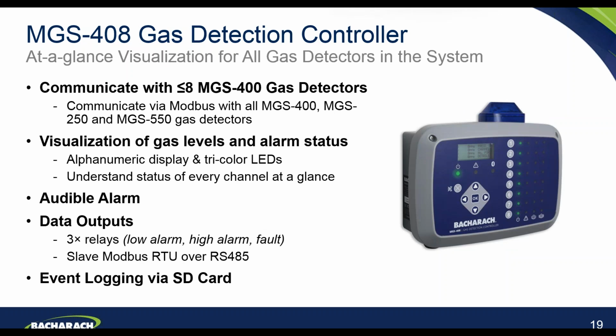Okay, so in addition to the detectors themselves, we offer the 408 gas detection controller. This is designed to be a very simple to understand and operate device for the customers. And it provides a simple at-a-glance visualization of all gas detectors that are connected to the control panel. So the control panel can communicate with up to 8 MGS-400 series gas detectors. It communicates via Modbus, so what that also means is that it has the added benefit that you can interface Bacharach's MGS-250 and also MGS-550 gas detectors into that control panel as well.